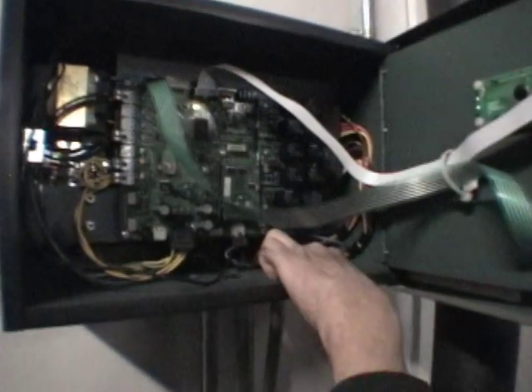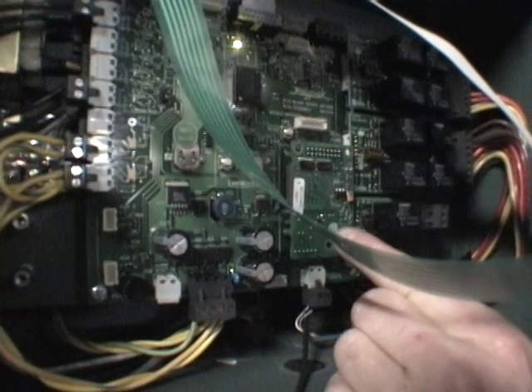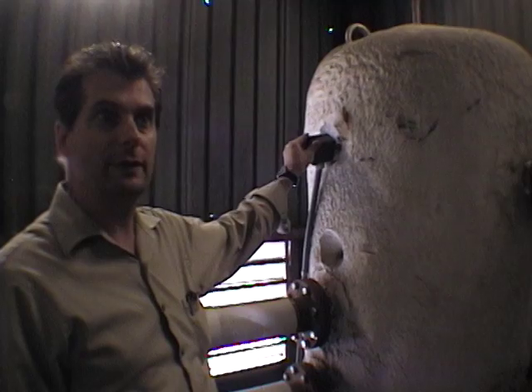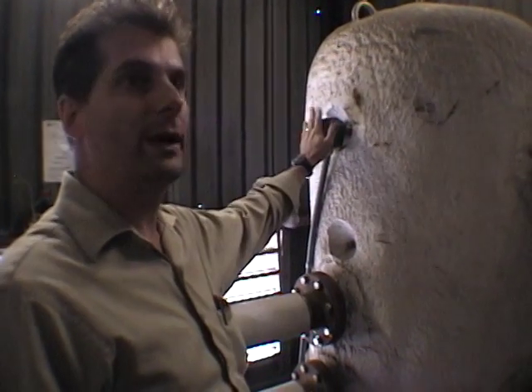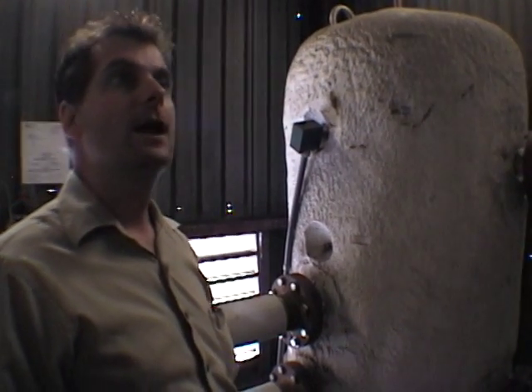This little card here — you can see the LonWorks wire, or network wire, connected to this little card, which allows us to remotely monitor and control this boiler controller over our network. It monitors this so he knows what temperature it is, and then he's able to talk to the boilers and say, give me a little more here, or I'm okay. This is just like a smooth... it's a buffer tank. It smooths the curves of the up and down. Correct, exactly. It pulls like a reservoir.